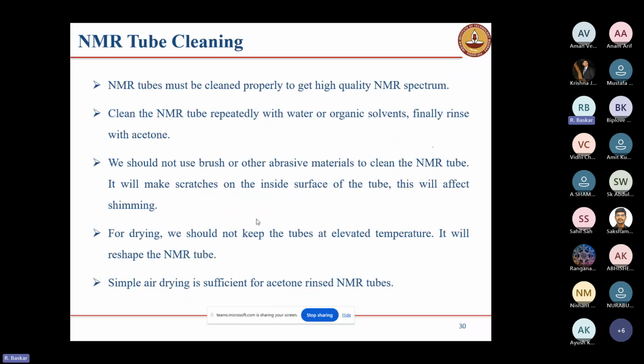Next is NMR tube cleaning. We have to clean the NMR tube properly. For cleaning, we use water and organic solvents, and finally rinse with acetone. We should not use a brush for NMR tube cleaning, because it will make scratches inside the tube and affect the shimming. For drying, we should not keep it in the oven. If you keep it for a longer time, the camber tolerance will get poor and the shape will change, which will affect the shimming. Simple air drying is enough. Once you have washed it, keep it overnight at room temperature, all the solvents will evaporate, and you can use it the next day.